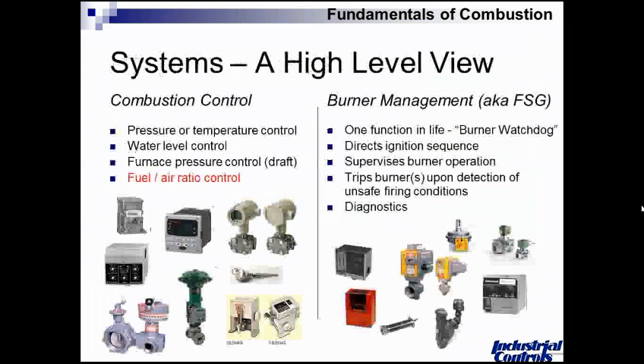When we think about entering this topic, I want to break it down into two major subsections. Just about any combustion application will consist of the combustion process itself, the combustion control, and a burner management facet. The burner management system — also known as a flame safeguard or FSG — exists essentially for one purpose: to supervise the purge, the ignition, and the automatic operation of a burner. It is there as a safety net to trip the burner upon detection of any safety-related failure.